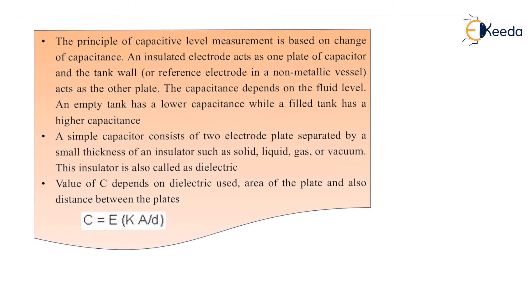The principle of capacitive level measurement is based on the change of capacitance. As the capacitance level changes, the level of the liquid changes. An insulated electrode acts as one plate of the capacitor and the tank wall acts as the other plate. An empty tank has lower capacitance while a filled tank has higher capacitance. A simple capacitor consists of two electrode plates separated by a small thickness of insulator such as solid, liquid, gas, or vacuum.